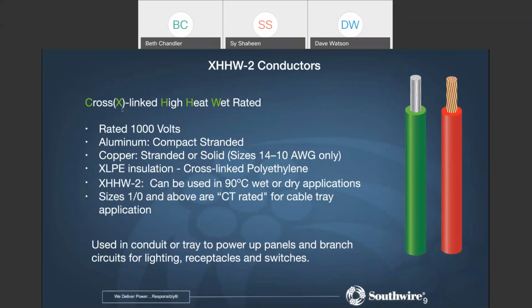These products are rated for 1,000 volts now. This has been in place for, I think, about a year and a half, close to 2 years at this point. Aluminum is compact stranded again, so this is available in copper or aluminum, just like the THHN style conductors. 90 degrees C, wet or dry applications. Again, CT rated in sizes 1/0 and above. And next slide.